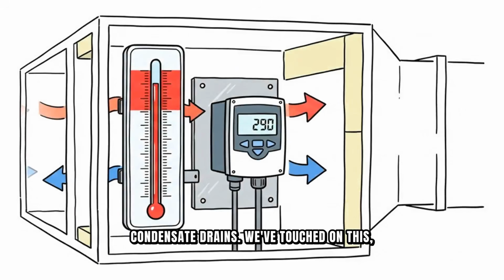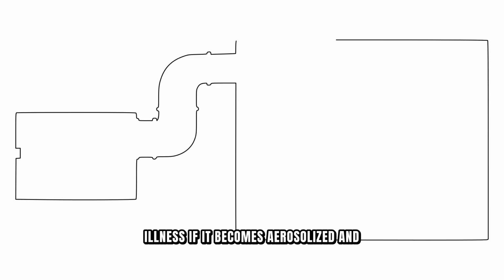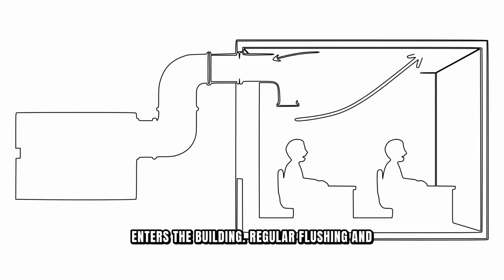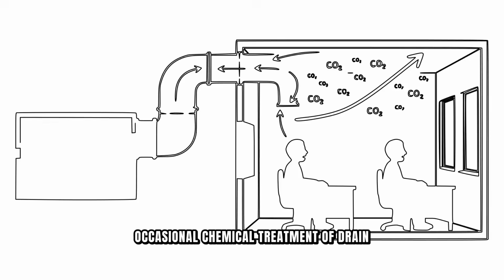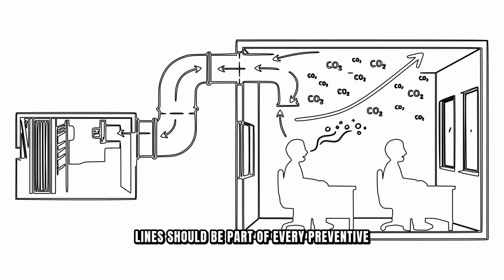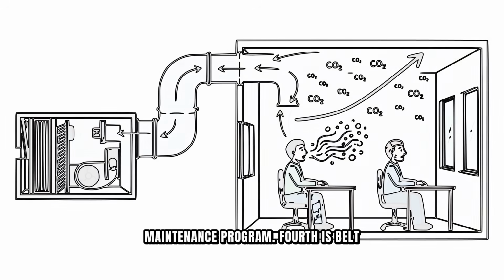Third is clogged condensate drains. We've touched on this, but it's critical. Stagnant water in the pan breeds Legionella bacteria, which can cause serious illness if it becomes aerosolized and enters the building. Regular flushing and occasional chemical treatment of drain lines should be part of every preventive maintenance program.